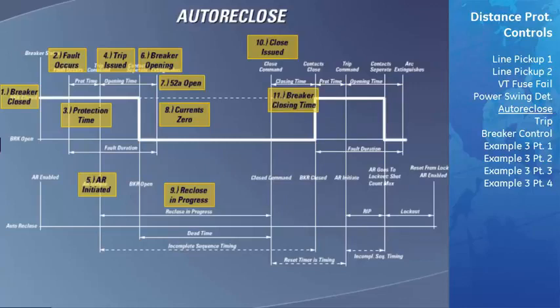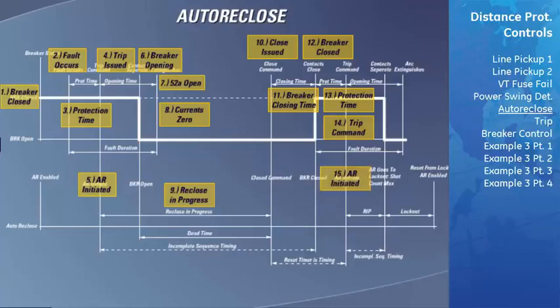The D60 will get an indication of the closing through its contact inputs. If the fault is still present, it will take some time for the protection algorithms to identify the fault. When the fault is identified, the D60 will again issue a trip. At the same time, an auto reclose gets initiated again, which starts the reclose in progress status. The breaker takes some time until it completely opens and signals the D60 through its auxiliary contacts. The D60 will now lock out the auto recloser. The recloser will now need to be reset before any other reclosings will be allowed. The auto reclose scheme has the following settings for each breaker that should be considered for each application.